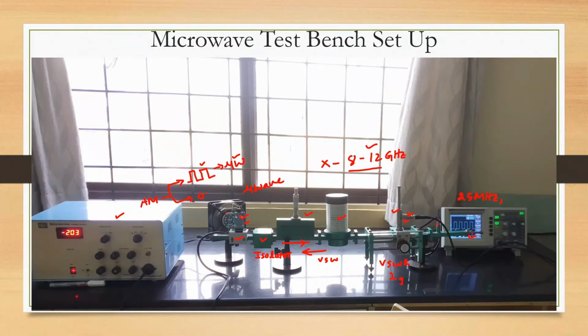and variations in the square wave we can map to our microwave signal measurements, like the amplitude levels, attenuation, then the dip in the signal when you are rotating this frequency meter. So using the variations in the waveforms, we can determine different parameters.